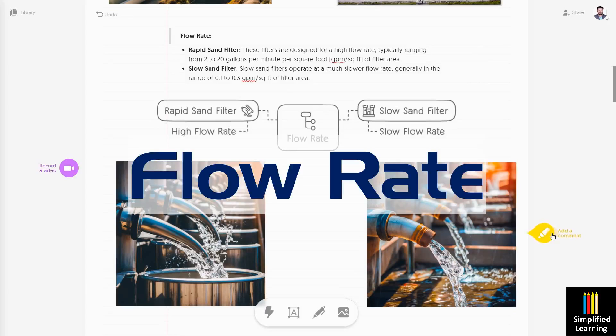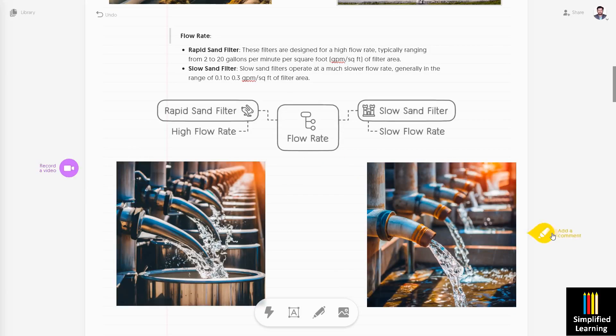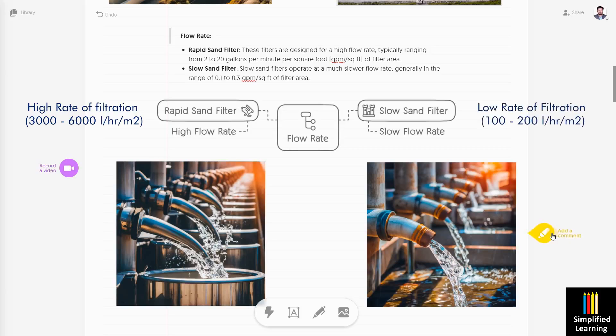Let's talk about flow rate. The prefix 'rapid' in rapid sand filter reflects its high flow rate, ranging from 2 to 20 gallons per minute per square foot. Whereas slow sand filter has a flow rate in the range of 0.1 to 0.3 gallons per minute per square foot. High flow rate is the property of RSF and slow flow rate is the property of SSF.